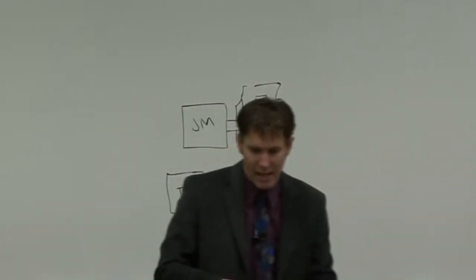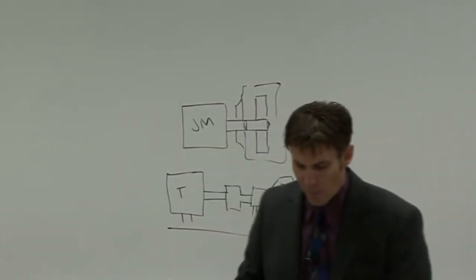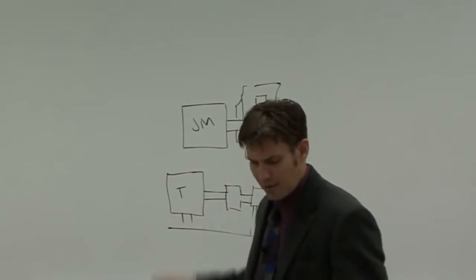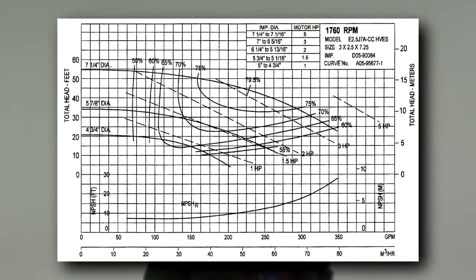So I've picked a closed coupled pump because of the size of my motor for this application. But let's just look at this curve. We've got a lot of different lines. First of all, let's look at the impeller trim. The impeller trim shows from 7 1/4 inch diameter down to 4 3/4 inch diameter.